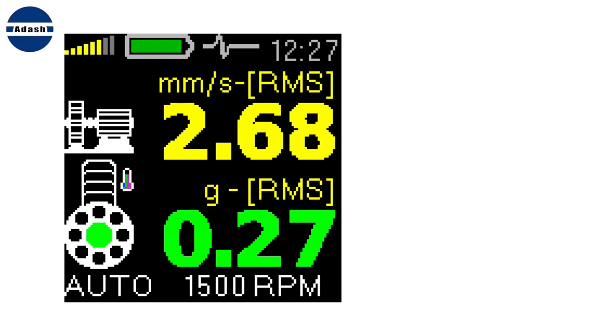You can take first reading once you prepare your points. Take two values from each point. The velocity value in millimeters per second or inch per second and the acceleration value in g. The velocity value is measured in frequency range from 10 to 1000 Hz. It gives us information about mechanical failures like unbalance, misalignment and looseness. The acceleration value is measured from 500 Hz to 16 kHz. It contains information about roller bearing condition.